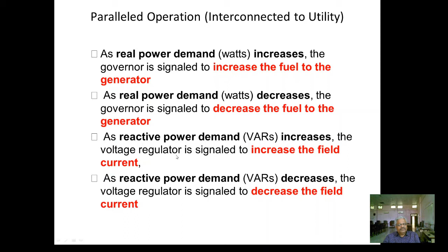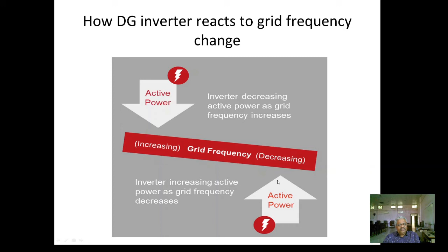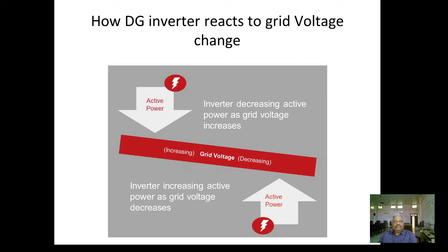In case of distributed generation, what happens? We'll see, for a distributed generation inverter. If the grid frequency decreases, what will this inverter do? It will increase the active power. And if the grid voltage decreases, it will also increase the active power. Means whether there is a decrease in the grid voltage or a decrease in the grid frequency, the active power from the inverter will increase. And whether there is an increase in the voltage or an increase in the frequency, the inverter will decrease its active power. Means the DG inverter is trying to control the change in frequency and voltage by changing the active power of the inverter.